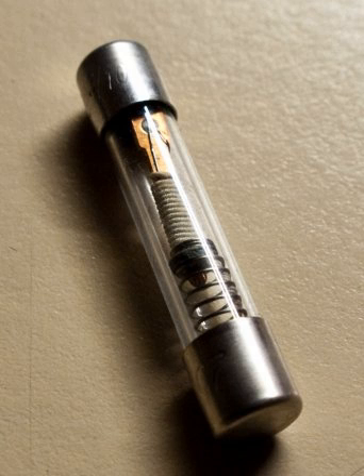Topic: Construction. A fuse consists of a metal strip or wire fuse element, of small cross-section compared to the circuit conductors, mounted between a pair of electrical terminals, and usually enclosed by a non-combustible housing. The fuse is arranged in series to carry all the current passing through the protected circuit. The resistance of the element generates heat due to the current flow. The size and construction of the element is empirically determined so that the heat produced for a normal current does not cause the element to attain a high temperature.